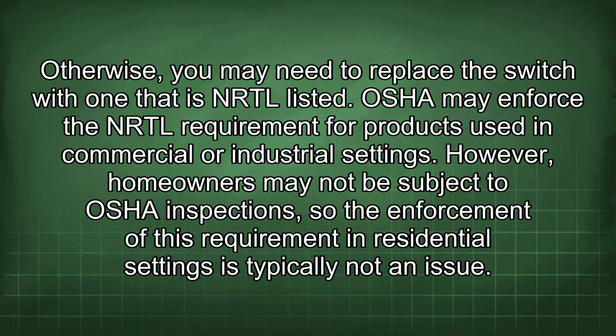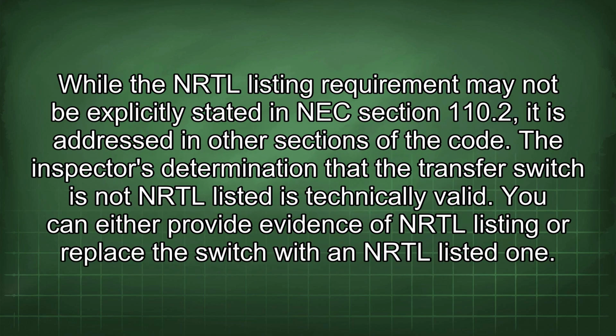not an issue. While the NRTL listing requirement may not be explicitly stated in NEC section 110.2, it is addressed in other sections of the code. The inspector's determination that the transfer switch is not NRTL listed is technically valid. You can either provide evidence of NRTL listing or replace the switch with an NRTL listed one.